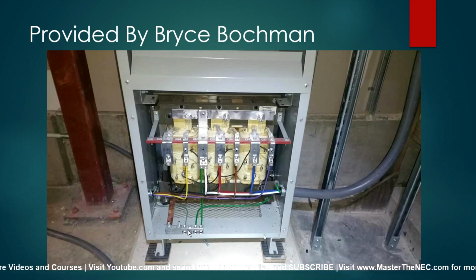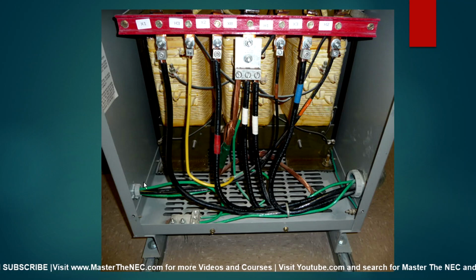Why can the grounding electrode conductor go here? Because he's using a wire type system bonding jumper, and code allows that under the exceptions to the rule, right? Okay. So that's good to go here. And let's see here. In this installation, they're coming in, and I don't know what method's being used here, but he's using a bonding lock nut. But again, if this is a punched hole, then you saw that these conductors, if they are over 250 to ground on the primary side, say 480, then it wouldn't require anything. If you weren't using those exceptions, okay, and you went to 250.92(B), then this would be a viable option if you were doing that.